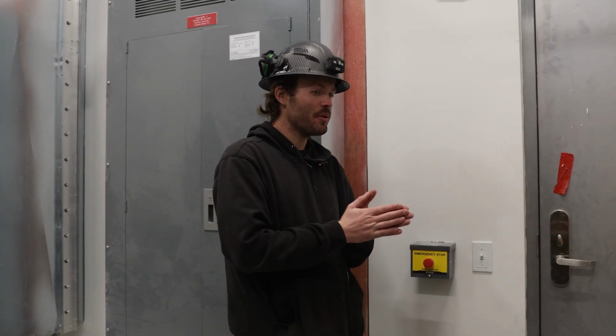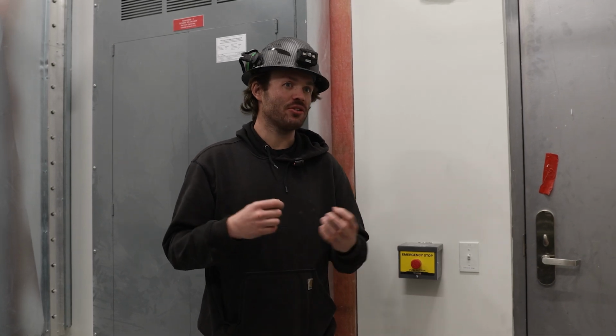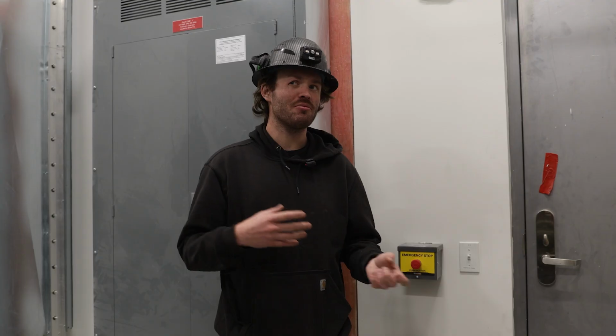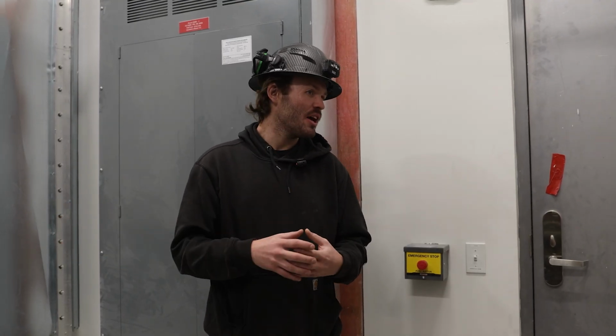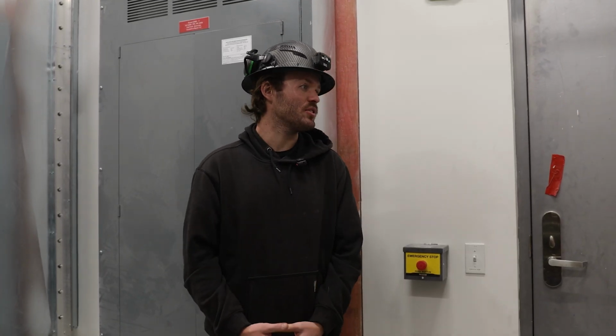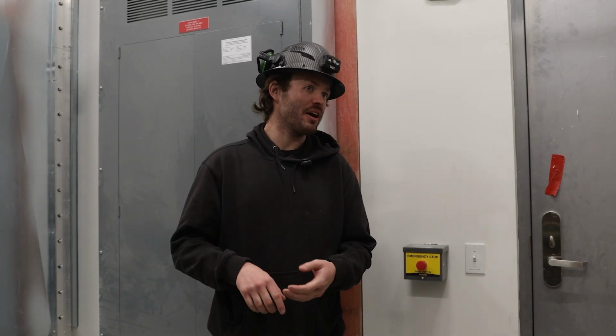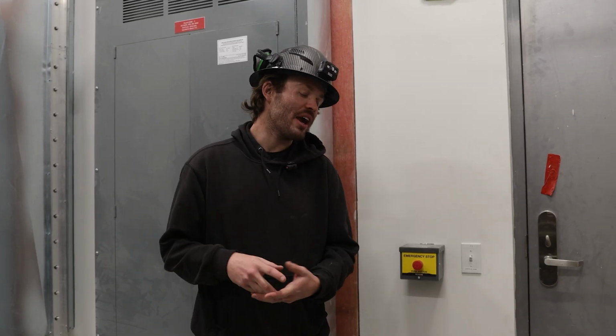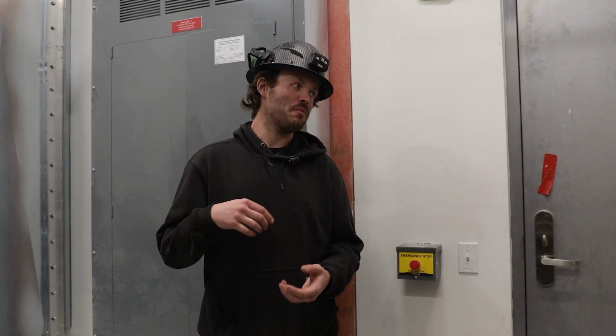Semi-annual inspections are to be done as well by a certified person, so a generator company. That's kind of the way the servicing will work: you'll do 5 monthlies yourselves probably. At 6 months, a generator company comes out and does a semi-annual, a monthly with a lot more checks, a more thorough inspection of the batteries, and a transfer test as well. Then 5 more monthlies go by, and then it's the annual servicing, where you get new oil, new fuel filters, load bank, transfer tests, inspected, tested. Every 5th year a quintennial service is required. That is new antifreeze, a new thermostat, checking the valves, an insulation test of the generator end, and cleaning the radiator.